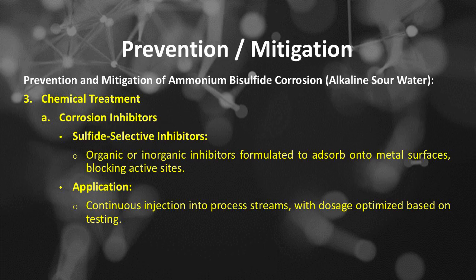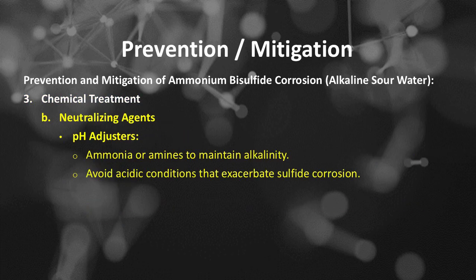Number 3 is chemical treatment, which includes, number A, corrosion inhibitors: sulfide-selective inhibitors, organic or inorganic, formulated to adsorb onto metal surfaces, blocking active sites. The application of corrosion inhibitors is by continuous injection into process streams, with dosage optimized based on testing. Number B is neutralizing agents, using pH adjusters, ammonia or amines to maintain alkalinity and avoid acidic conditions that exacerbate sulfide corrosion.